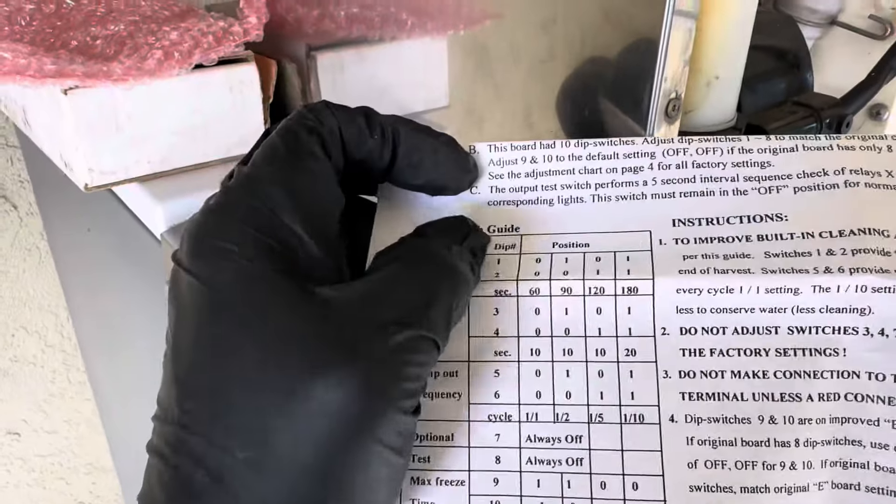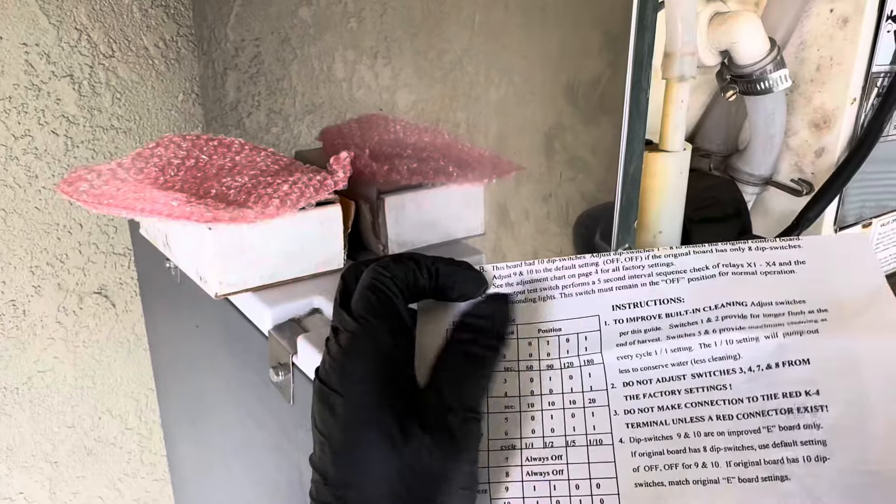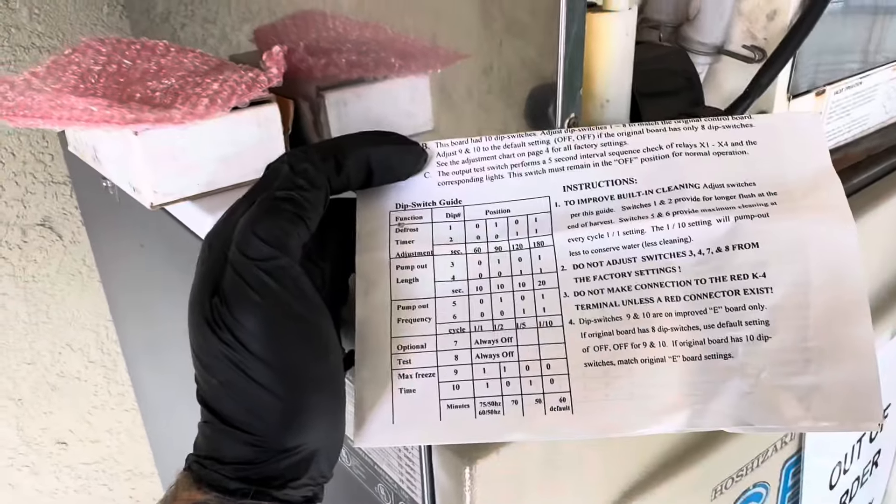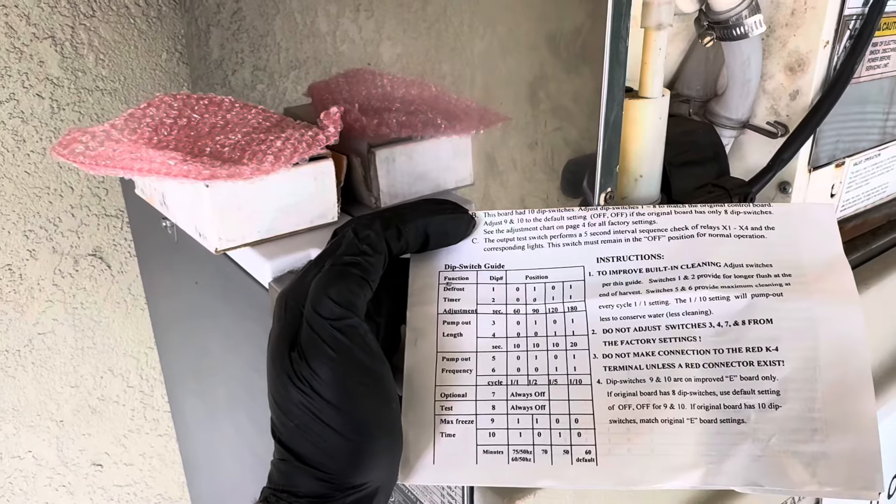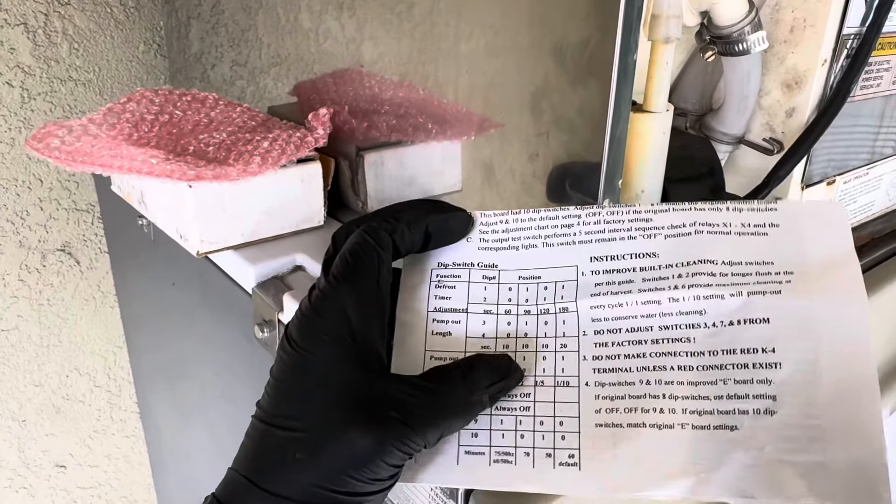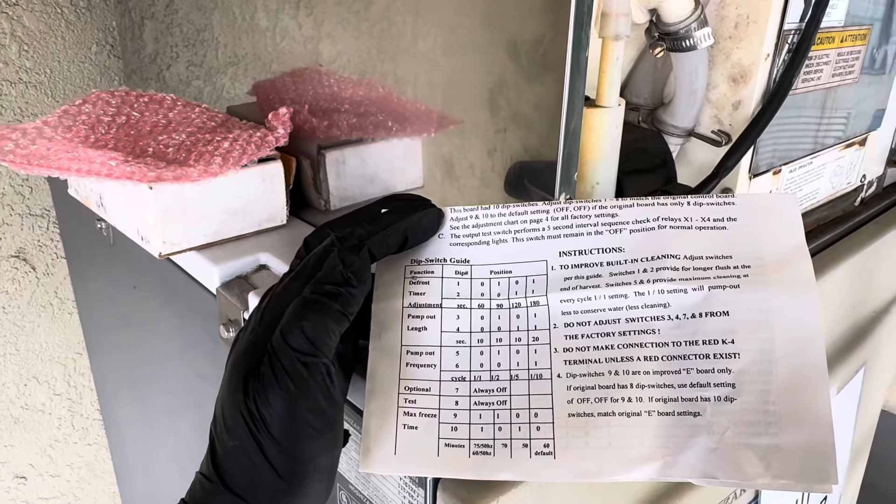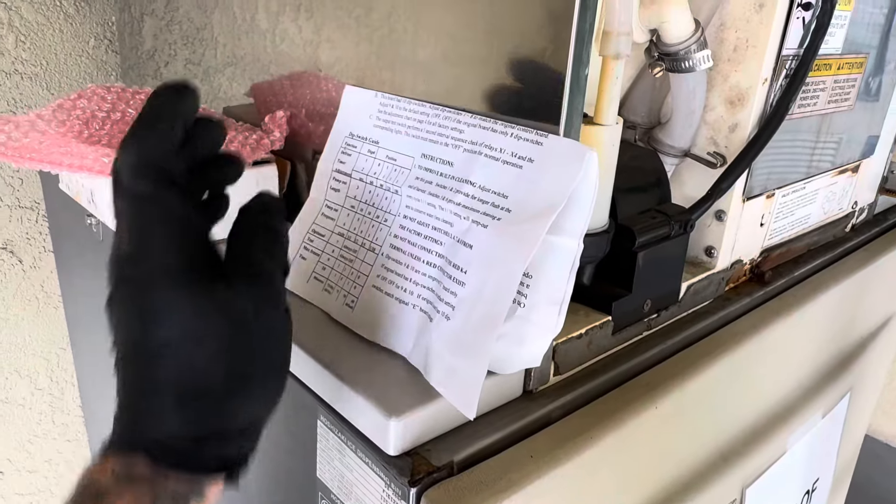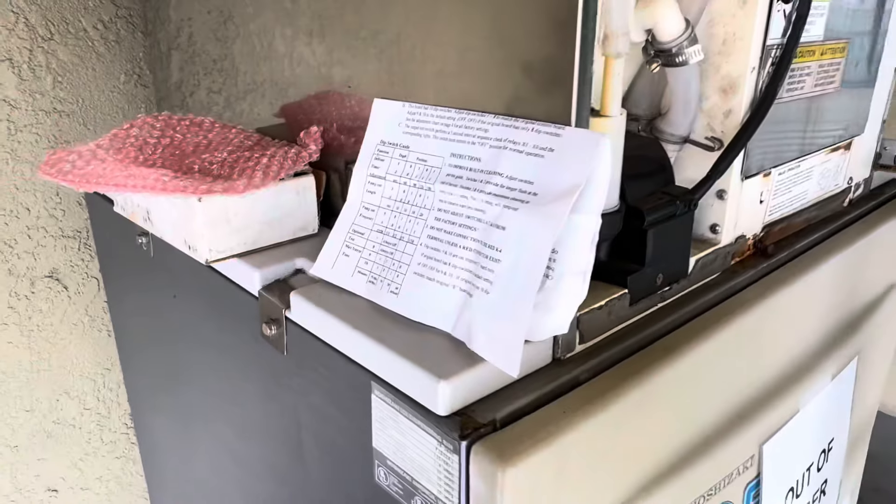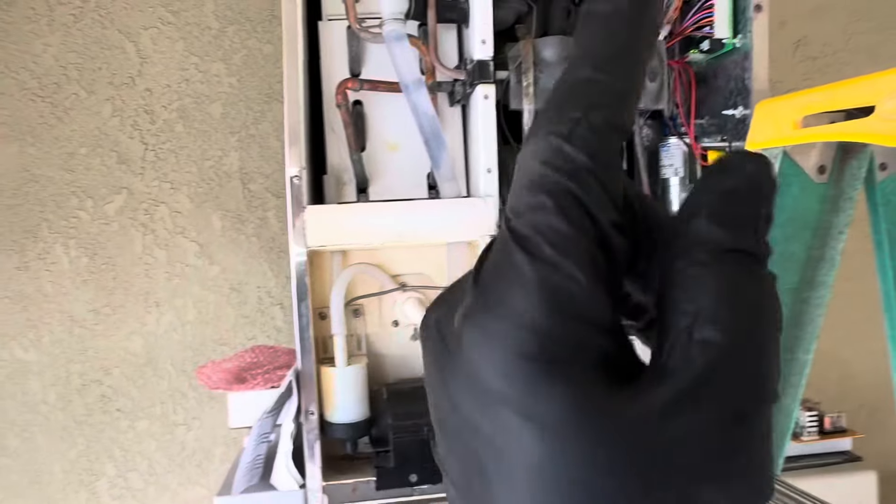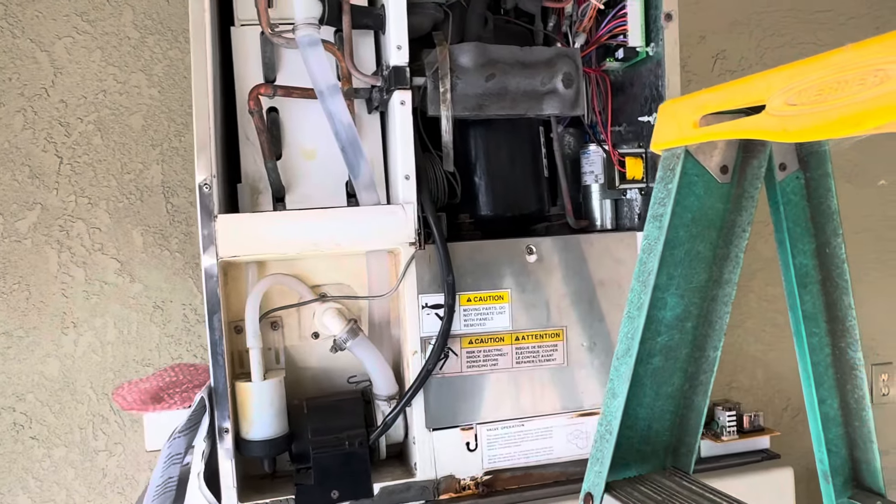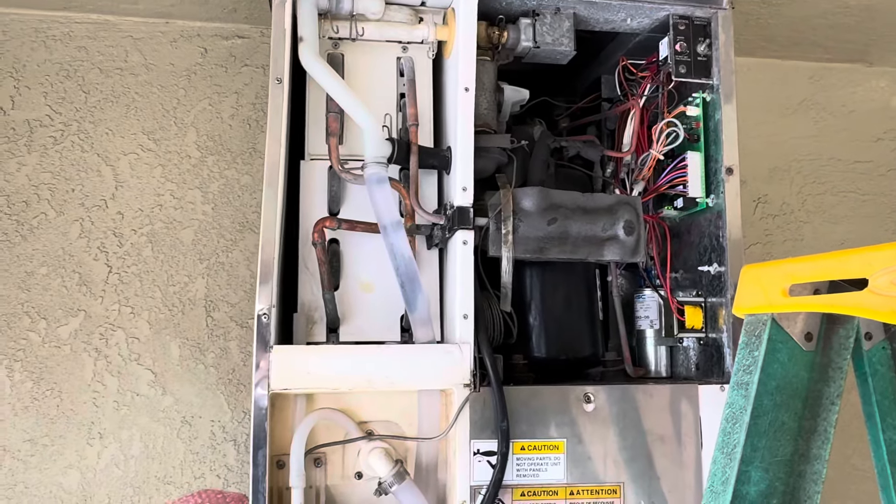You can change these settings up too. If your machine's using too much water and they're getting on you for water, you can change up some of these settings, especially the pump out frequency. You probably want to put 5 and 6 at 1 and 1. That might save you some water. They've been really hitting the water usage hard, and that's a problem with Hoshizakis, is the water usage compared to like a Manitowoc.